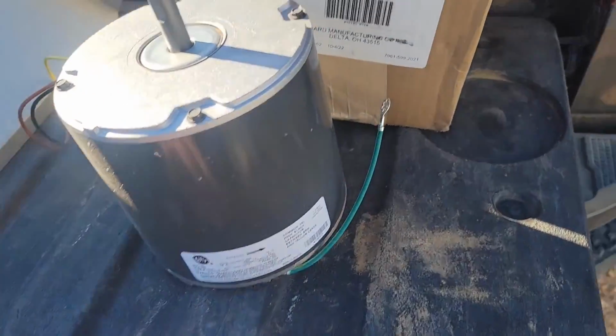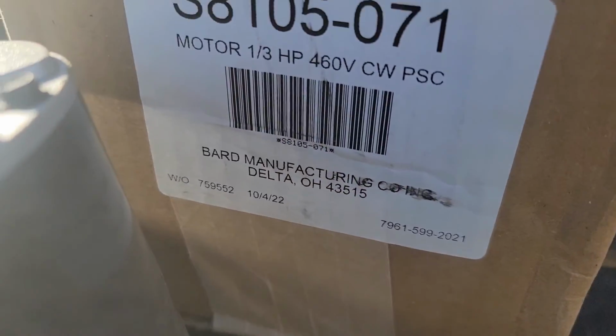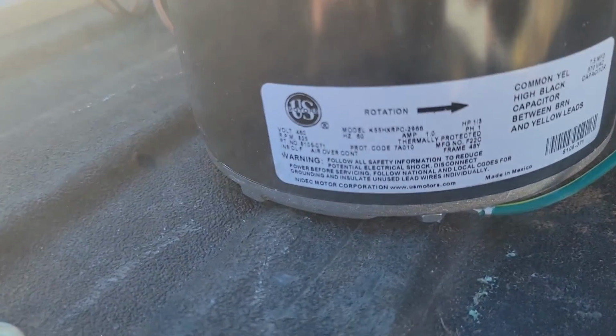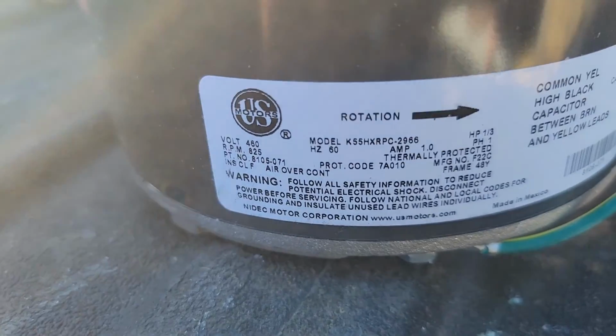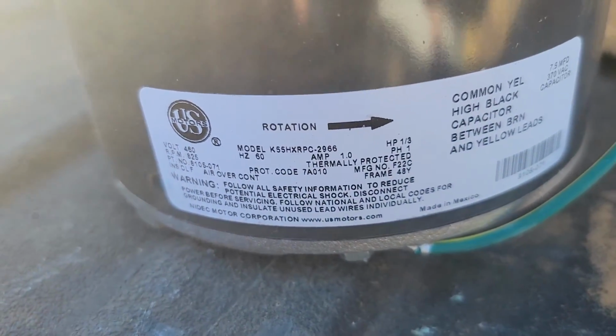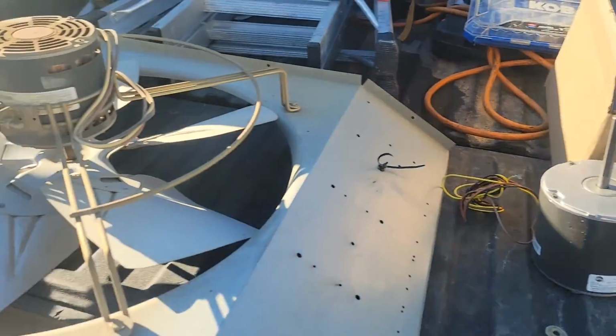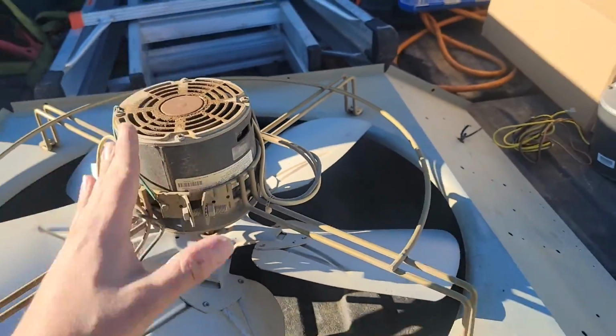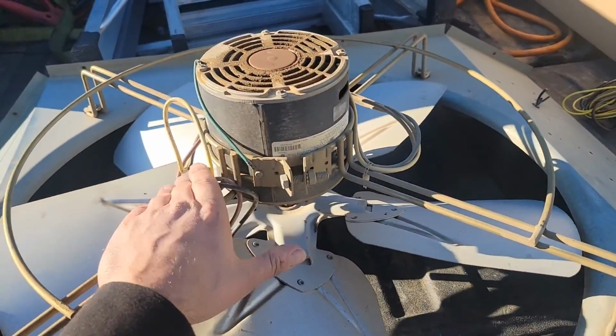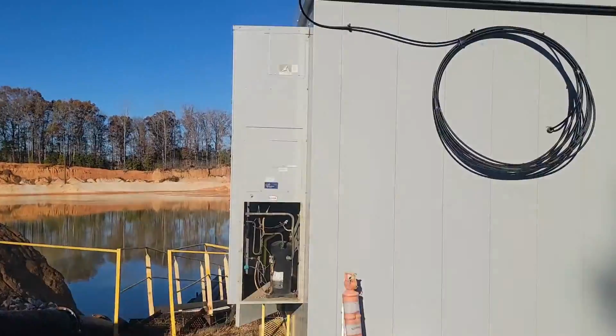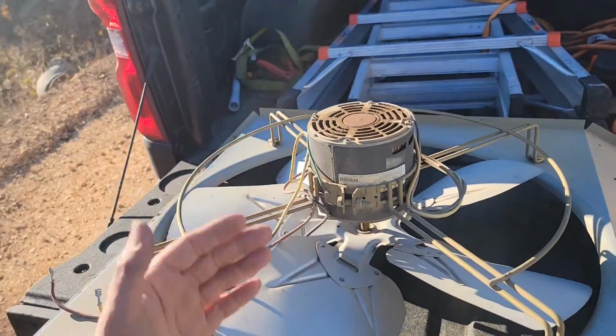I'm gonna get this fan, we're gonna get this Bard unit back up and running. Back on site, got the new motor, Bard Manufacturing, 825 RPM, 460 volt, 1/3 horsepower, single phase condenser fan motor. I'm gonna go ahead and put it in the housing here, the bracket, and then we'll put it in the Bard unit and see what we got.